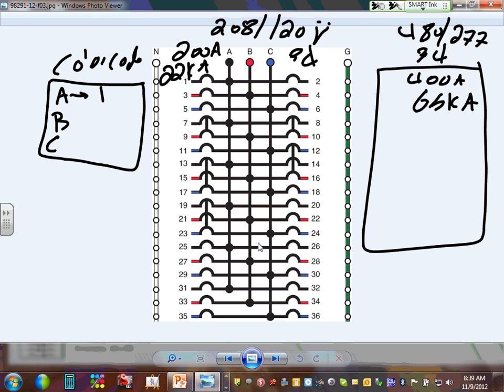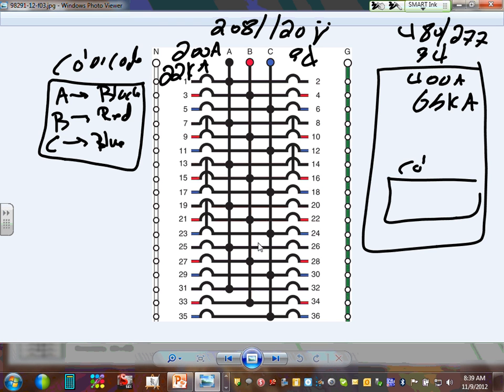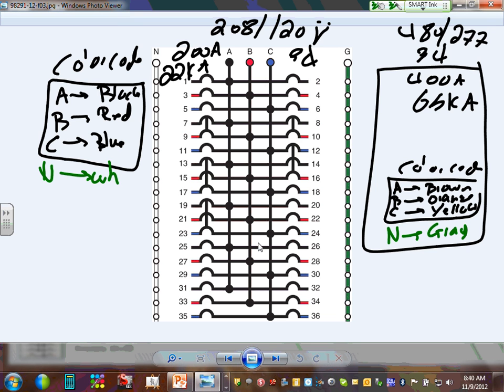This is going to be black. This will be red. This will be blue. You go right here on the face of that panel, color code. Phase A is going to be brown. Phase B is going to be orange. And phase C is going to be what? Yellow. Industry standard. And the last thing, guys, is neutral. It's going to be gray here. And neutral from this one is going to be white. This is required by code.